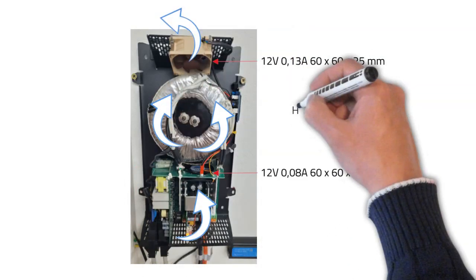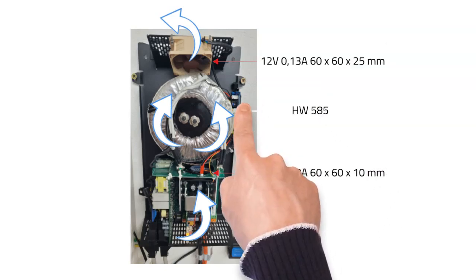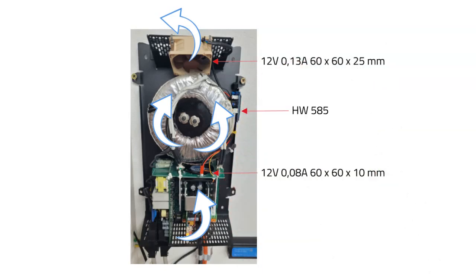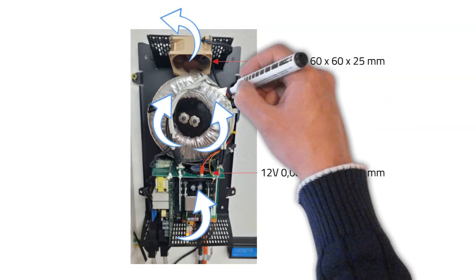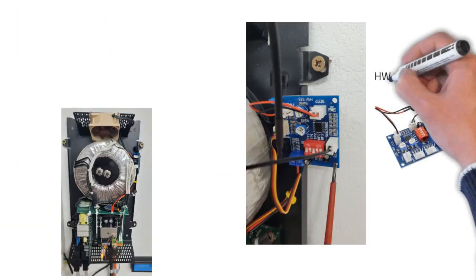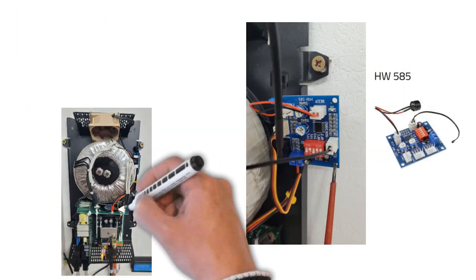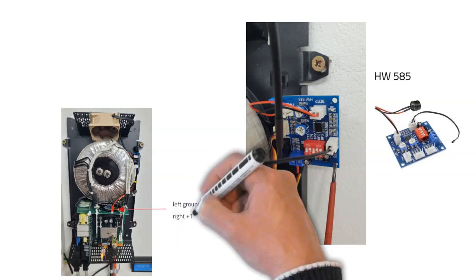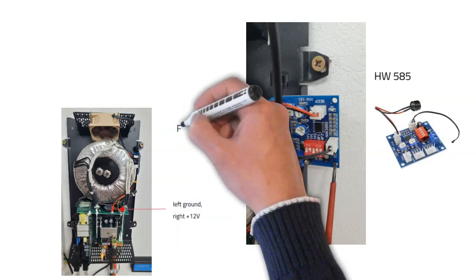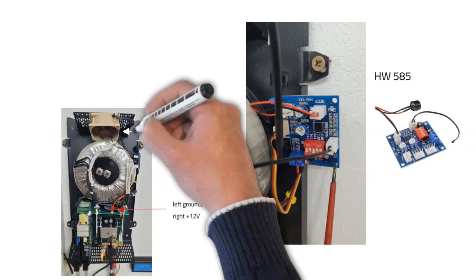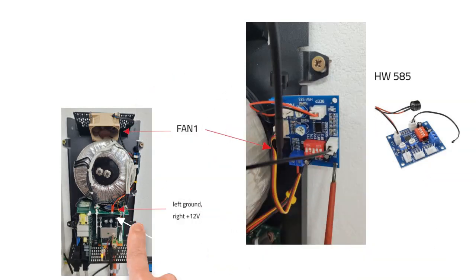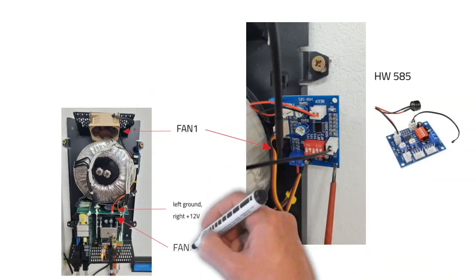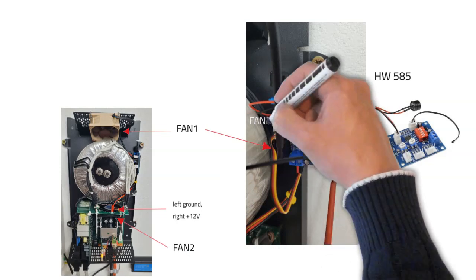The HW585 control and monitoring module can be placed to the right of the transformer. The temperature sensor is attached to the transformer. The fan control module is connected to the previous fan power supply. The correct polarity must be observed here. Fan 1 of the control module is speed regulated and is connected to the upper fan. The lower fan is connected to fan 2.